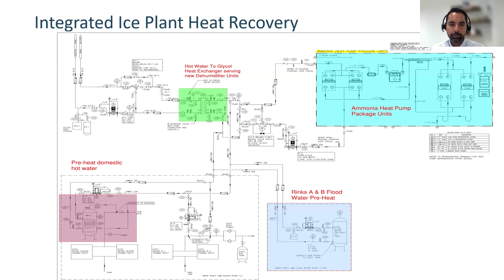So what we learned, and I think they mentioned it in the previous case study, is it's really important to have proper measuring data, proper metering, the proper run hours of your equipment, which in our case, we didn't have so much detailed data. So it was based on assumptions and recorded run hours. You need to create a real profile to see when new load is available, but also to monitor in the system that you're intending to use when their load is, what the demand is from them as well, and to create a proper profile to see when you can generate heat and when you can actually discharge it to the systems, and properly size the equipment to come up with the proper optimized size that will work in this case. So that's something I would encourage everybody to consider: proper metering and monitoring of equipment.